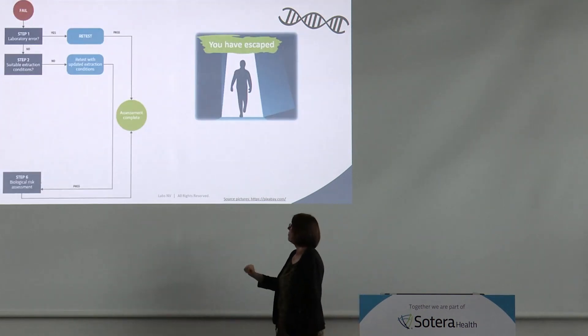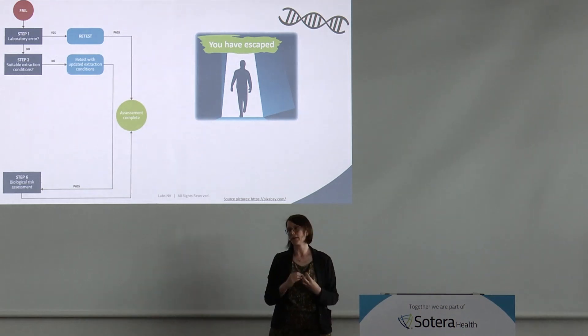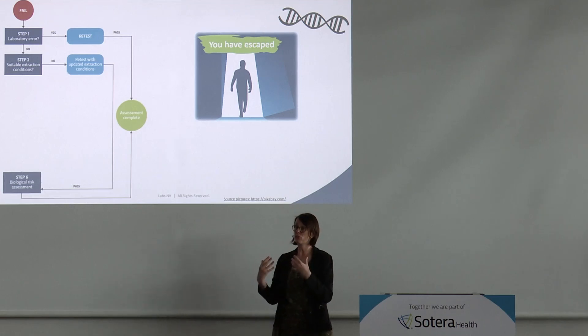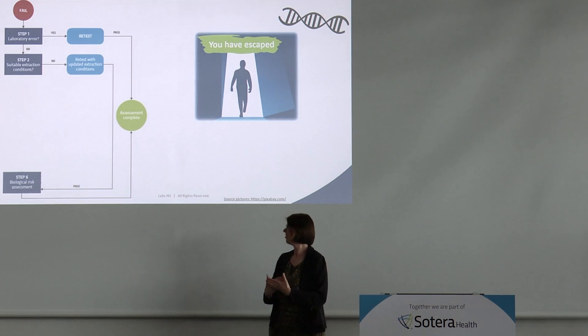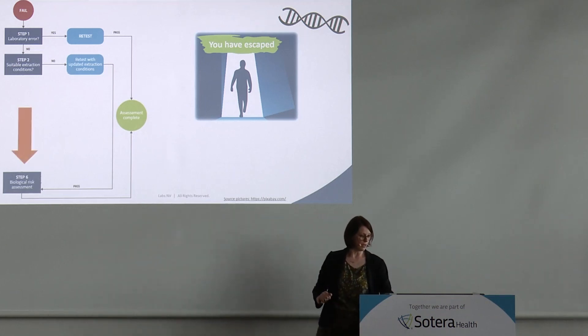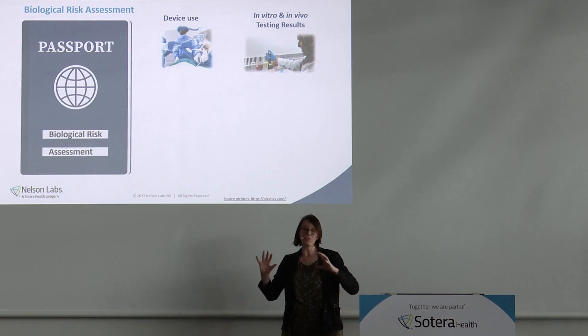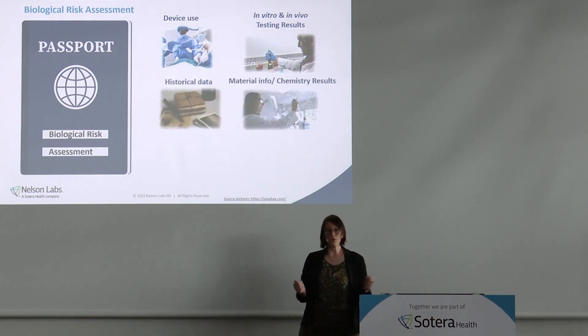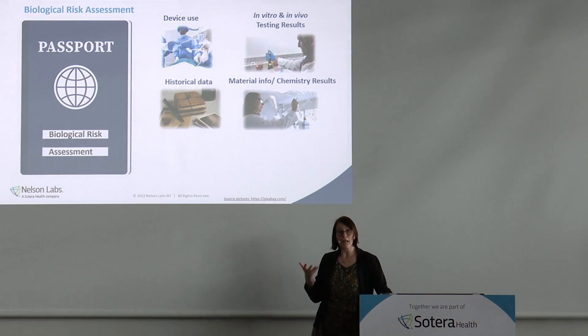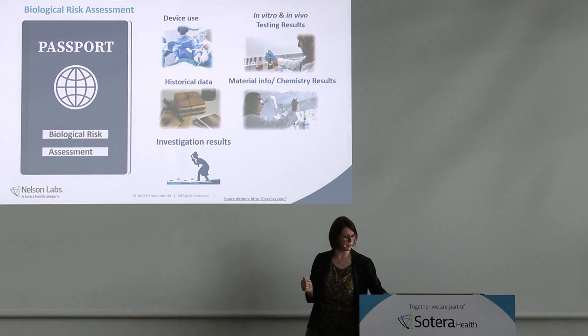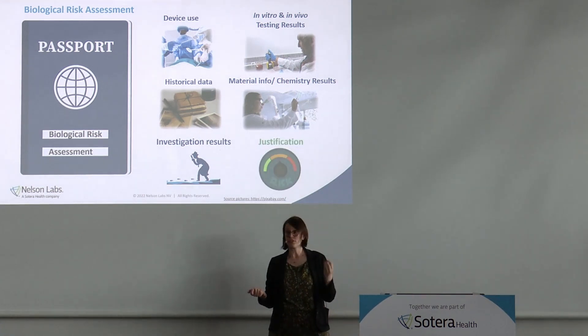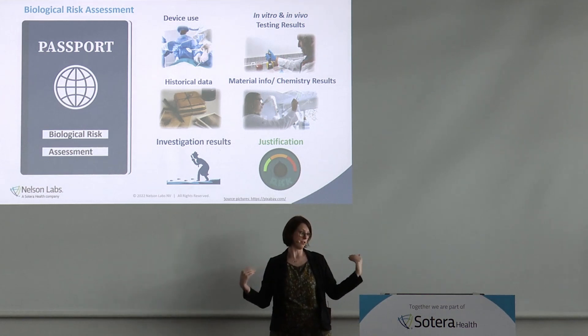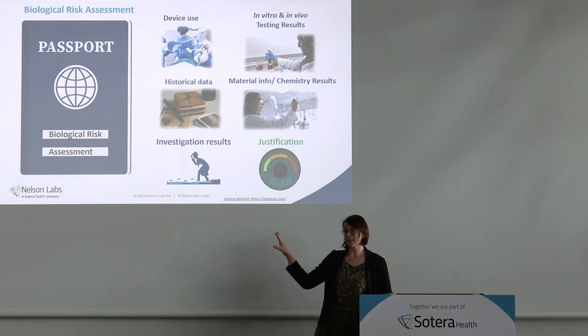Assuming the original extraction conditions were not appropriate and you retest with the right conditions — if you then have a pass, you're not completely out of the room yet. You still have to go through step six: the biological evaluation or risk assessment. You have to assess the risk of the device and create a kind of passport. This includes device use, in vivo and in vitro testing, historical data, material and chemical information, investigation results, and justification if you've changed parameters.